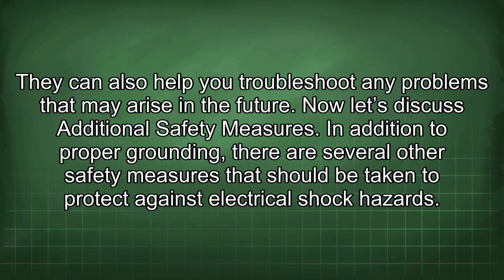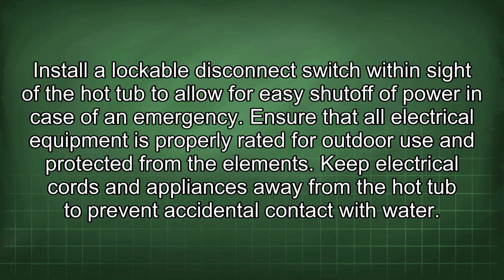Now let's discuss additional safety measures. In addition to proper grounding, there are several other safety measures that should be taken to protect against electrical shock hazards. Install a lockable disconnect switch within sight of the hot tub to allow for easy shutoff of power in case of an emergency. Ensure that all electrical equipment is properly rated for outdoor use and protected from the elements. Keep electrical cords and appliances away from the hot tub to prevent accidental contact with water.